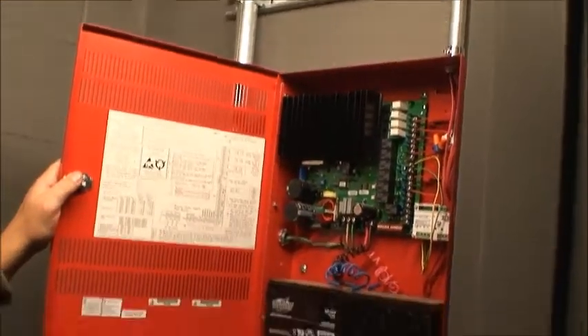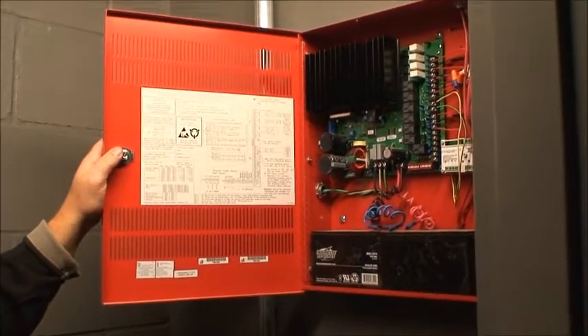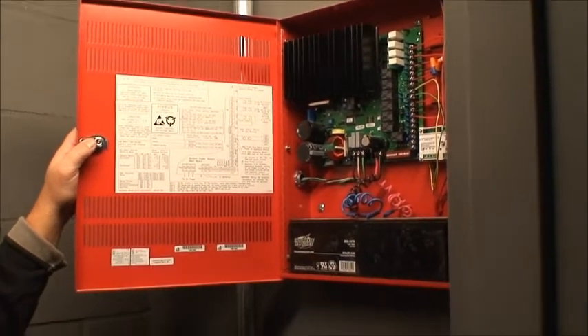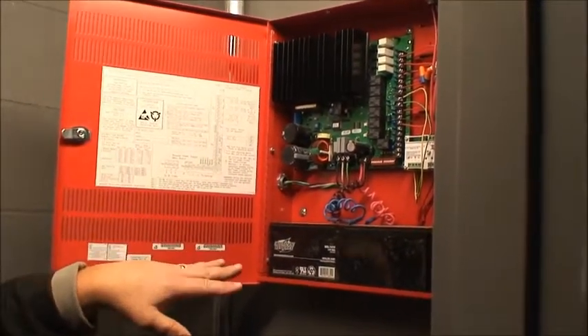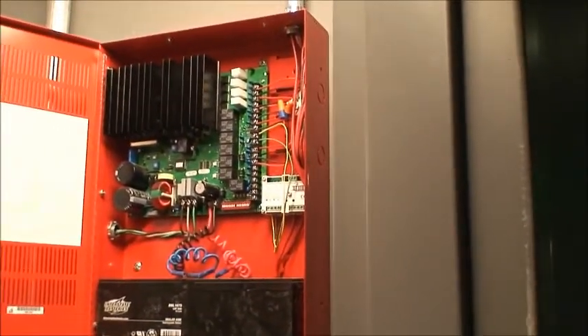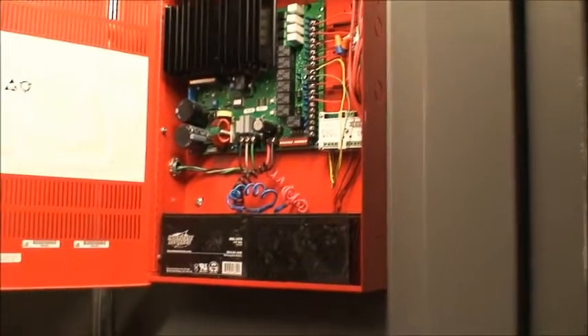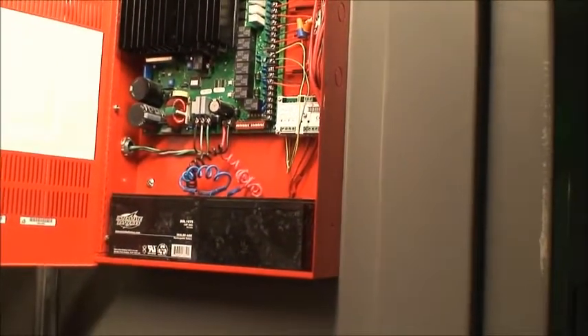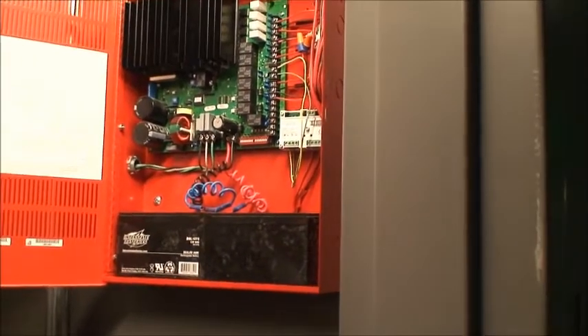So these little booster boxes up here, the fire boxes, right? With the strobe lights. Yeah, the horn strobes all get activated from the 2nd floor and 4th floor, from a signal in the main panel. But this provides us with more power because of the number of strobes. We wouldn't be able to do them all out of the main panel, so we need 2, what they call booster panels, to provide us with additional 24 volt power.